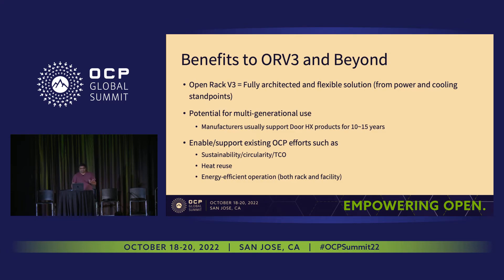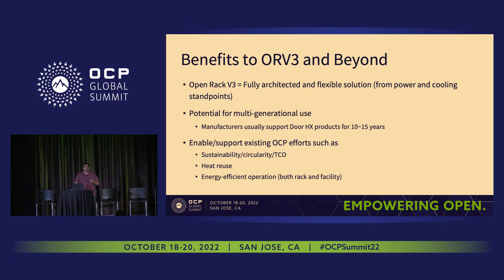Let's talk about benefits to Open Rack V3 and beyond. Open Rack V3 from the start has had a focus on enabling liquid cooling, so there's definitely a benefit to defining a door heat exchanger solution specific to it — giving us a fully architected and flexible solution when any end user decides to adopt Open Rack V3. Talking with vendors, we acknowledge potential for multi-generational use. A door heat exchanger solution could be in operation for 10 years or longer, and HPC customers in particular have very stringent reliability requirements — something that could be worked into this specification.